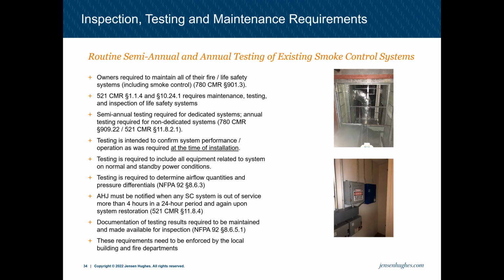527 CMR. Testing is intended to confirm that the system works as required at the time of the installation. So, as Tony had talked about, some of these system design intents have changed. The method for atrium exhaust and stair pressurization has changed over the last 20, 30 years. And the intent is that this testing ensures that it works as it was permitted and installed. So you don't need to retroactively ensure that it works as required by current requirements.